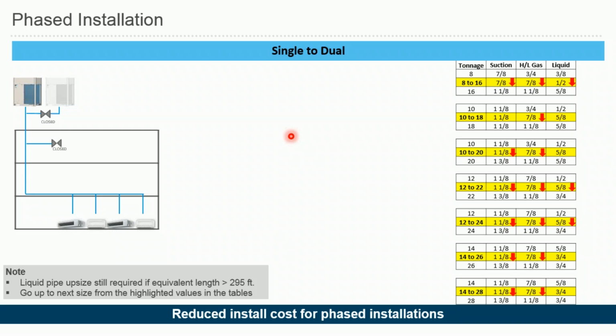We looked at these two things especially, and how we could make some improvements in our existing product lineup. We did some additional testing for proper oil return and refrigerant control, and we came up with these new rules and new pipe sizes for the phased installation feature. This will be mainly handled in WebExpress, our selection software. Right now, WebExpress availability for phased installation will be sometime in June, probably close to mid-June. But in the next few slides, I'll be showing you how this phased installation feature will work.